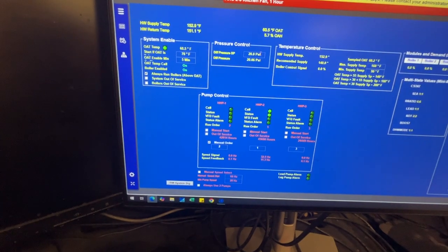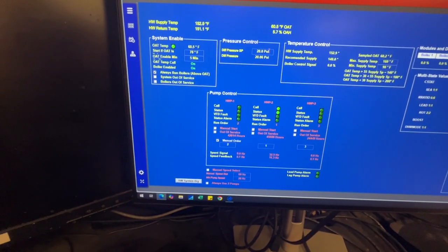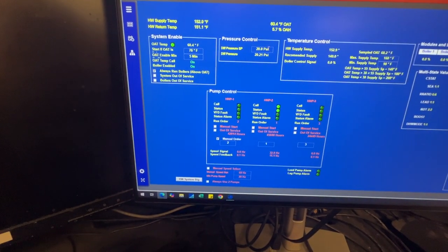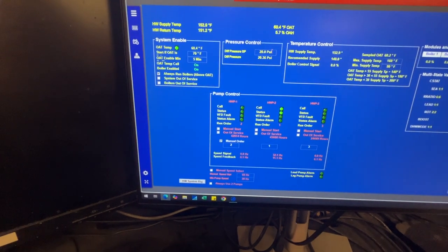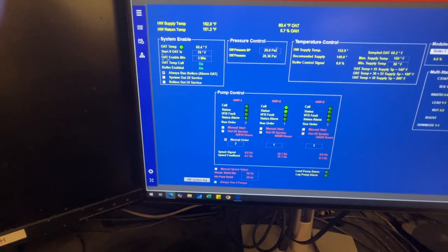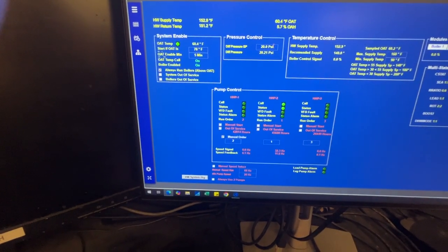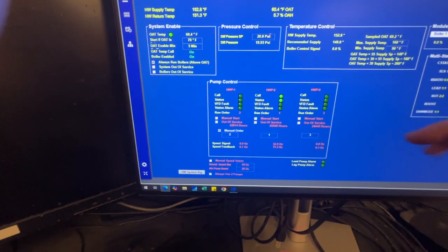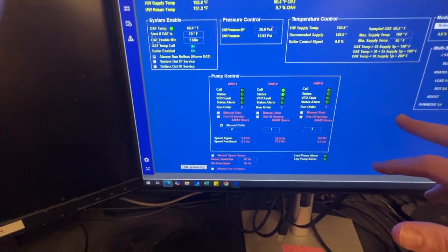So when it happens again, I would say that what we need to do is get mini splits that exhaust or put the condensers on the outside of the hotel, and that they pump cold air in there to keep those VFDs from failing.